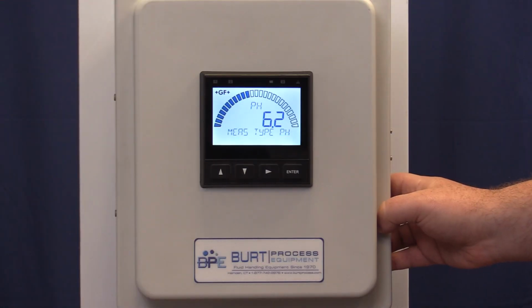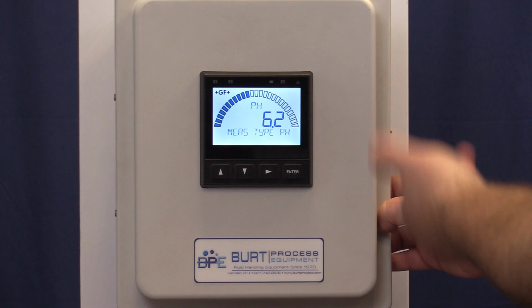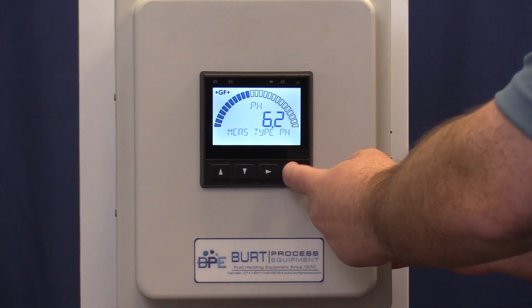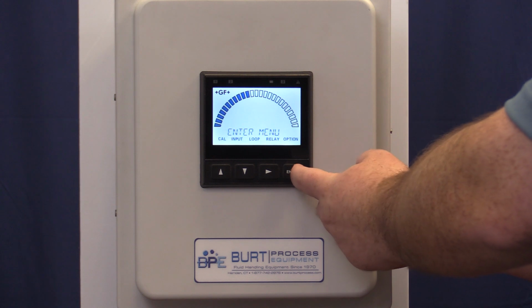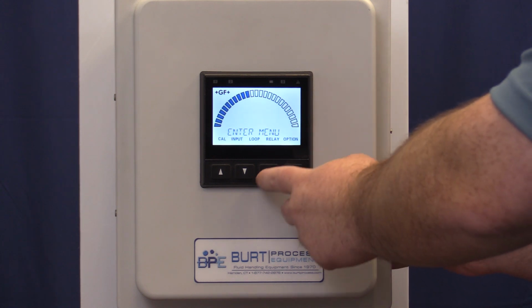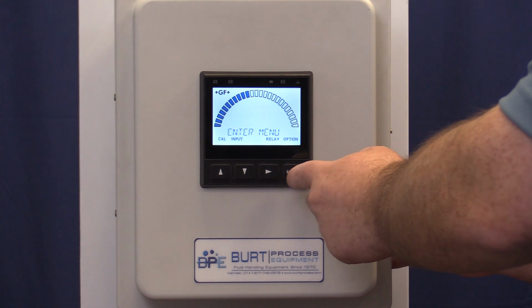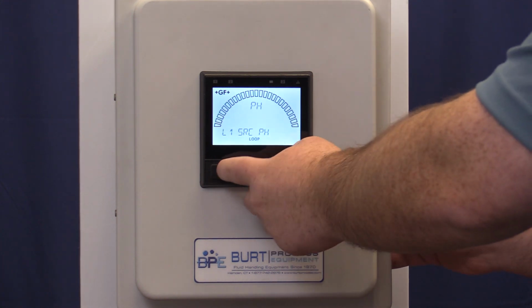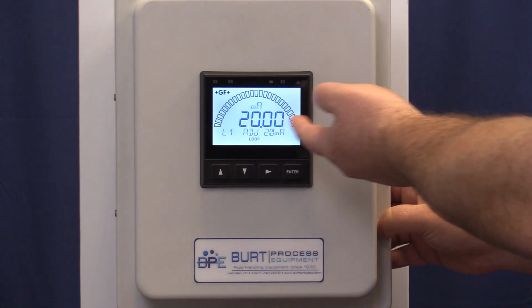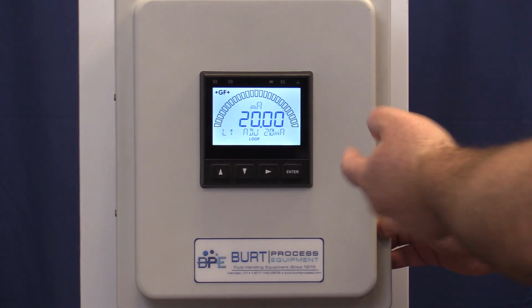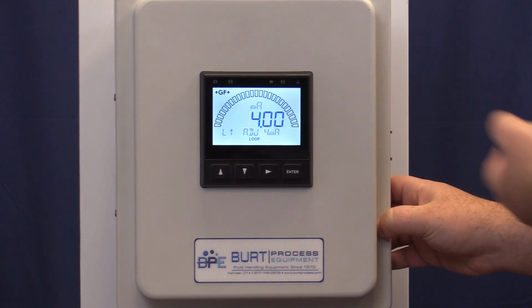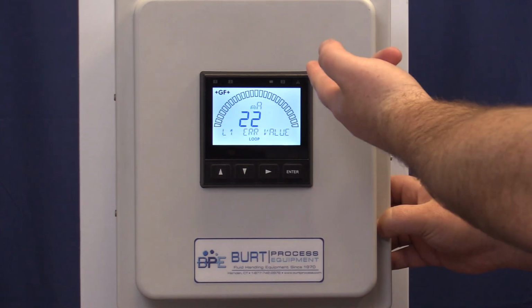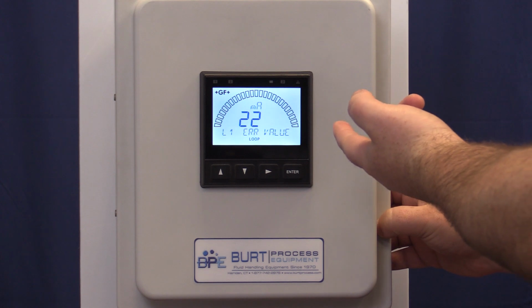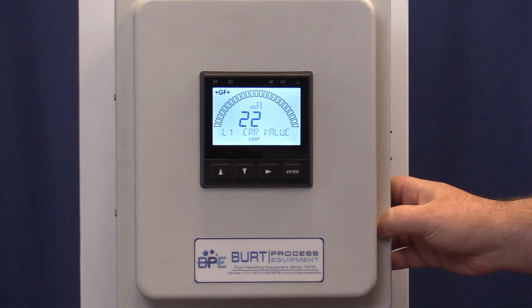So the sensor can only recognize values from 4 milliamps to 20 milliamps, so anything outside of that range is going to cause an error message. So if we start at our basic screen here and press enter for 3 seconds, it brings us to the menu options. We can go to loop to set up our 4 to 20. If we go up, we have 20 milliamps, which is a suitable value. We have 4, which is a suitable value, but then if you go to 22, since that's out of the 4 to 20 milliamp range, that's what's giving us our error here.